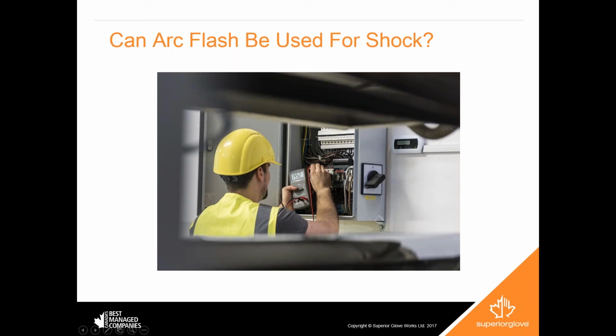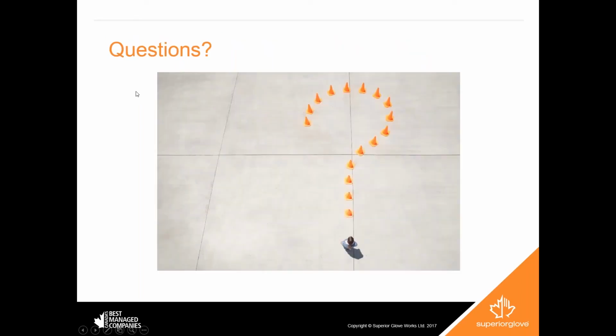Another question, and this relates back to, again, with rubber insulated gloves. Should you be wearing your arc flash gloves over those or under the rubber gloves? Well, I can tell you from just my years of experience in doing it, I've never seen anybody wear an arc flash glove in conjunction with an electrical shock glove, because if you're worried about shock and preventing an electrical shock, like I said, you're going to be wearing it can be a low voltage or a high voltage rubber insulating glove, and generally these are worn with a leather protector over them, and thus the need for the arc flash in conjunction with that is not needed as a rule. Now, I'll be the first to tell you, I am not an electrician, and that might be something better suited for a little more in-depth research, but this is the answers that I've gotten back from dealing with many of the electrical companies throughout the United States over the years.